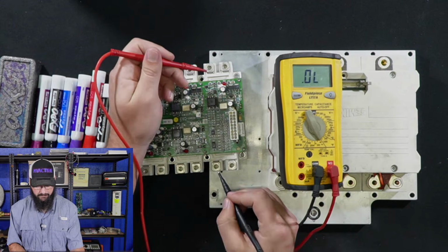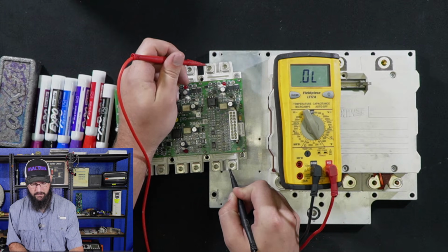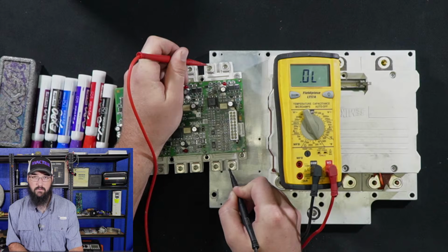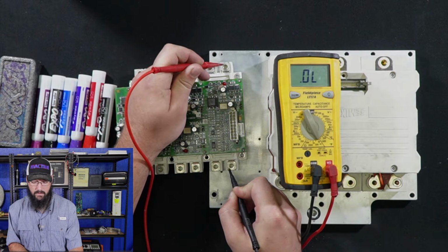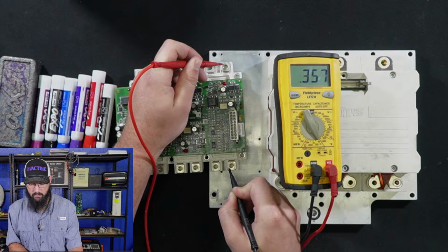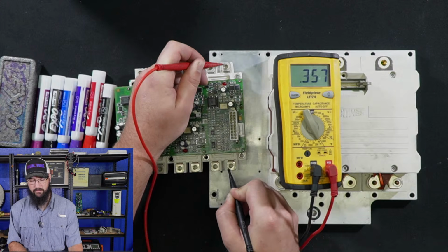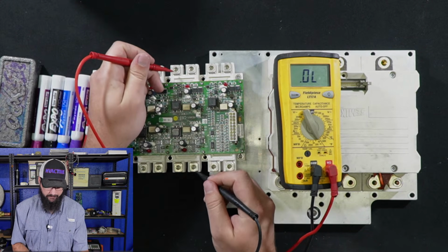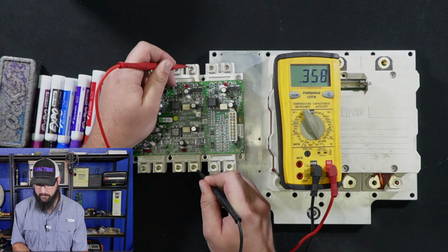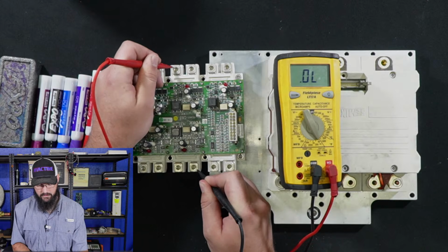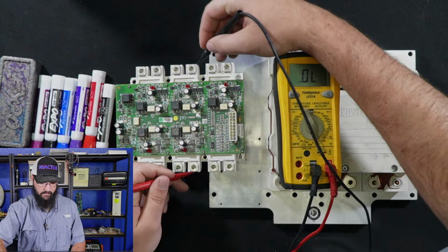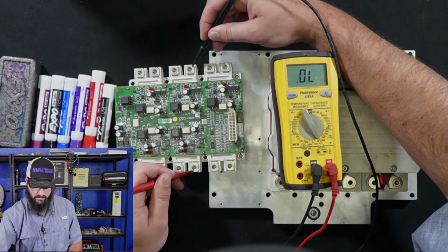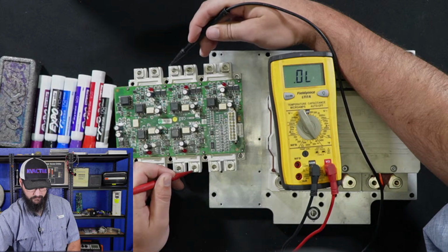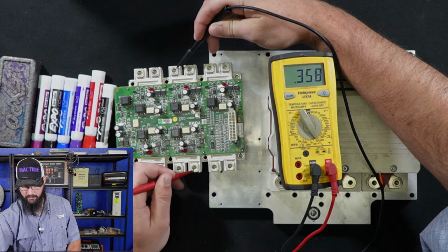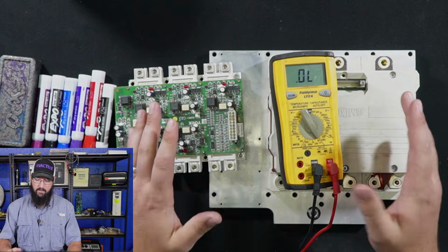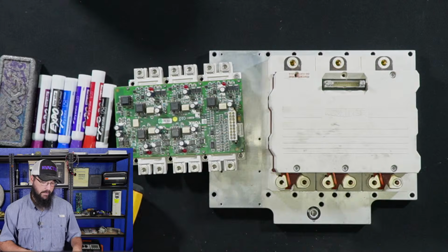Just to show that there's not a difference on this output side, I'm going to flip the leads around. Negative to my output, positive to my positive input. OL, cool. We had a reading once before, it was 0.36. And then this had OL before, but we have 0.36-ish, close enough. That's awesome. Let's try this other one. I'm going to do it reverse order. So we get a reading, 0.36-ish. OL, flip it around. OL, and 0.36. Do you understand my point here that I'm trying to show you?